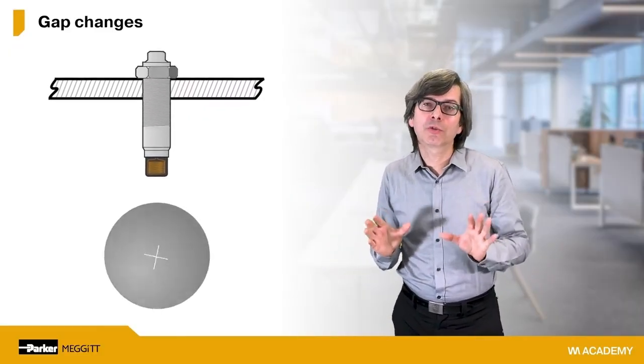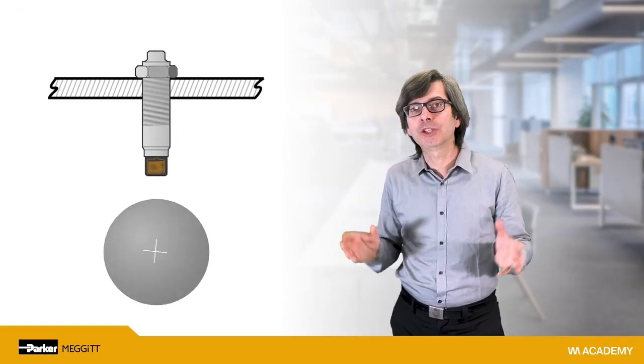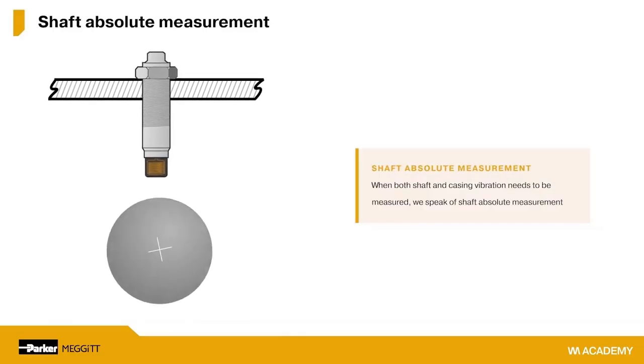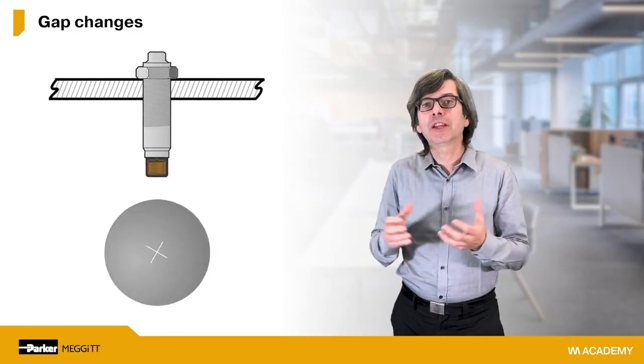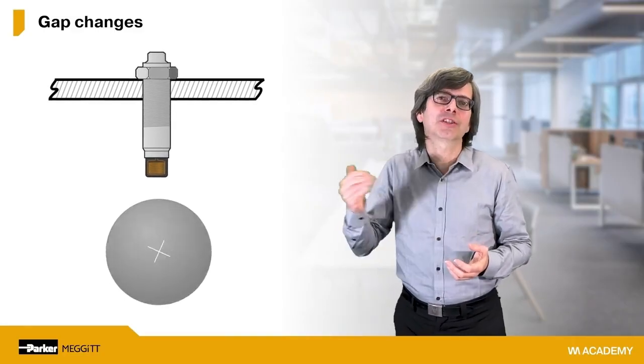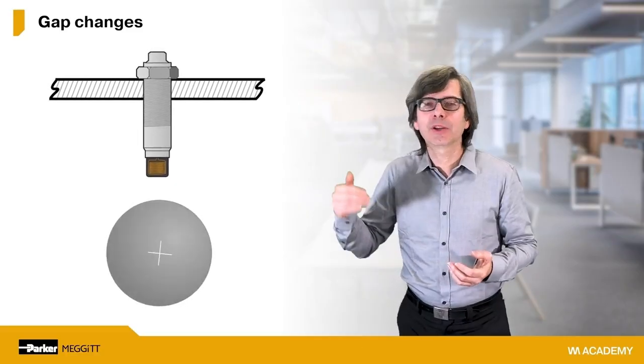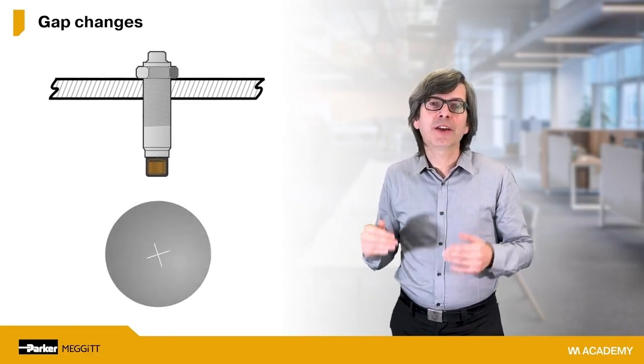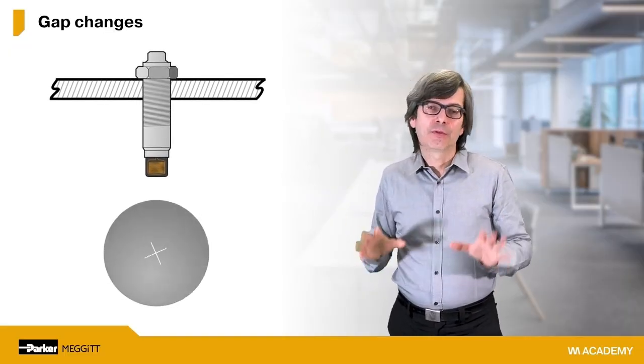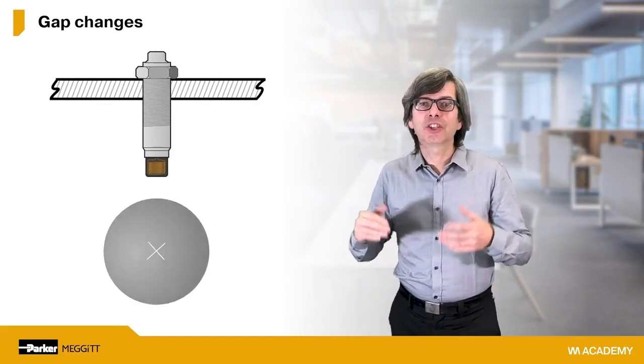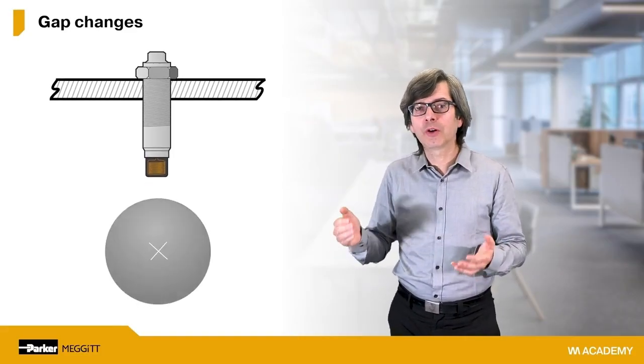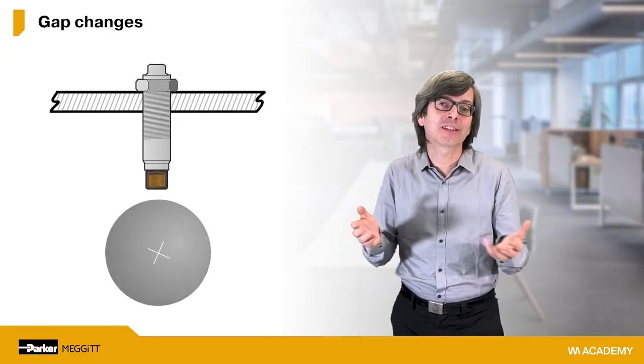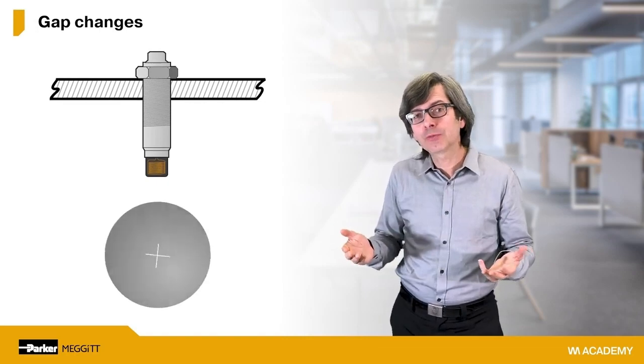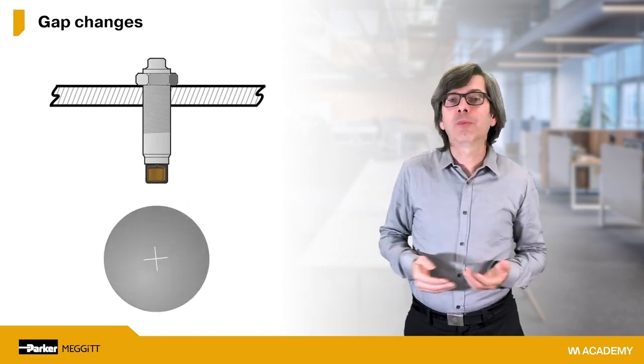But this is not always the case with highly compliant machines or with turbomachinery. And in such cases, both vibrations have to be measured and then summed vectorially into a composite measurement result. In a later lesson, we will show how the relative measurement made by a proximity probe can be adjusted using a separate casing vibration measurement to provide a so-called shaft absolute measurement. For now, however, it's enough to note that a change in the gap can occur due to movement of the probe, usually affixed to the machine casing, movement of the target, which is usually the shaft, or movement of both of them in parallel.